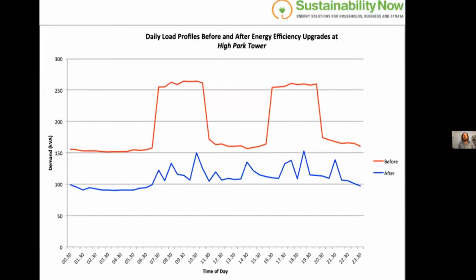Here's an example of their load profiles before and after. You can see in the red, this was their car park ventilation system operating via a timer. So it was running all the time from about 7 o'clock in the morning until about 10:30, and then again from about 4 p.m. until about 8 p.m. So this was all completely unnecessary. We were able to just essentially cut that right out with the carbon monoxide sensors.